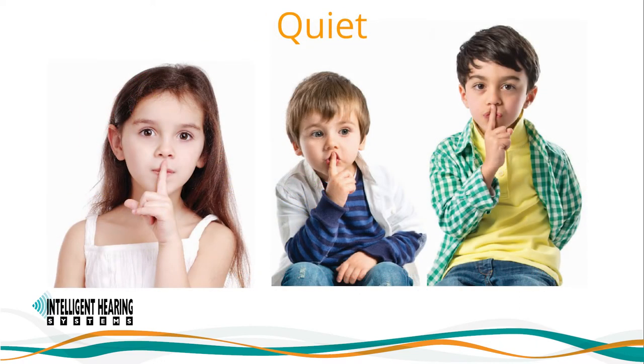Be sure the patient is quiet. This is an acoustical test that will be affected by acoustical noise such as talking, coughing, snoring, even rattles of movement and any audible noise present in the environment. Continuous background noise should be avoided. Random noise can be overcome by averaging and rejection settings, but it is important that if background noise exceeds 50 dB SPL, clinicians do not attempt testing. Find a quiet location first and instruct the patient to be as quiet and as still as possible during testing.